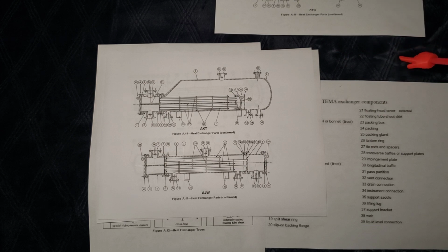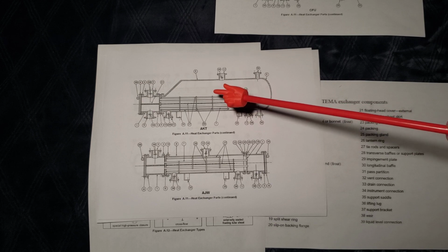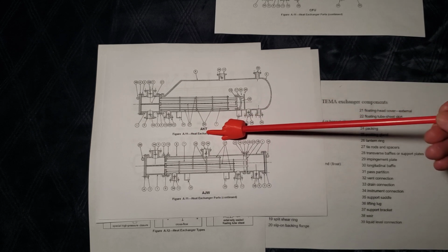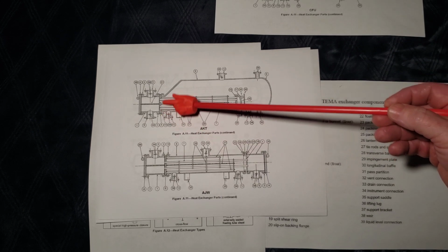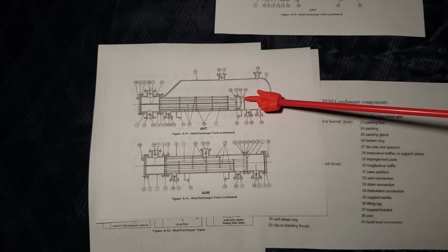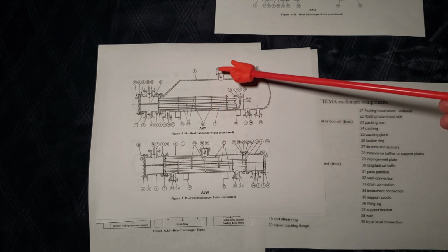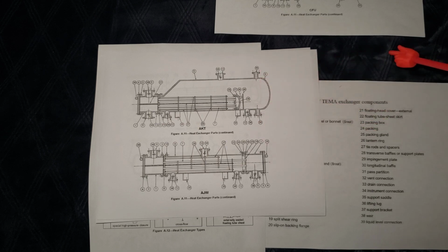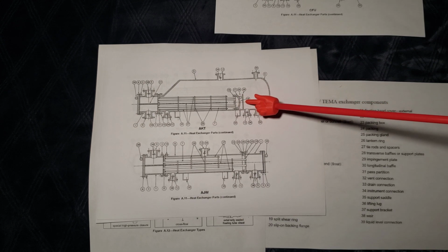That's the nice thing about these. And they can be used in both heat exchanger and in condenser configuration. Is that important? Well, it can be, but when we're describing it in our reports, if we use the letters that it is a 30 by 120 AKT carbon steel insulated heat exchanger, that goes a long way to describing this exact configuration.